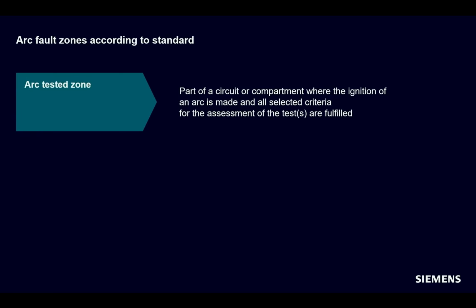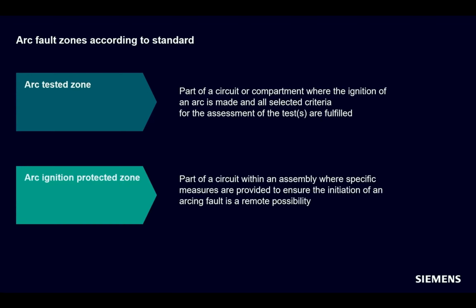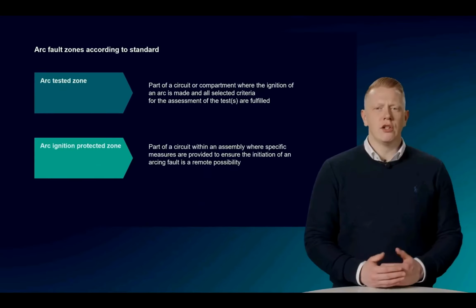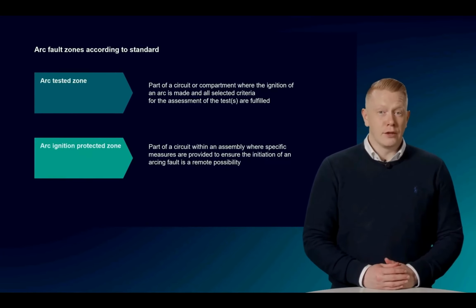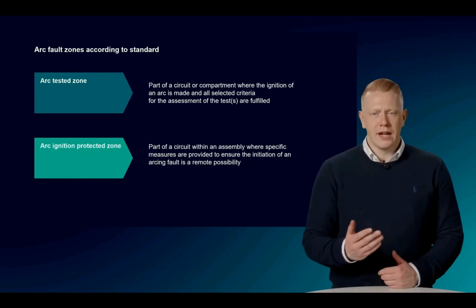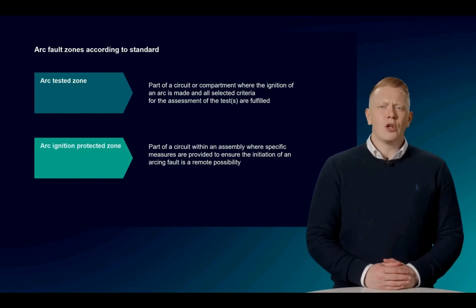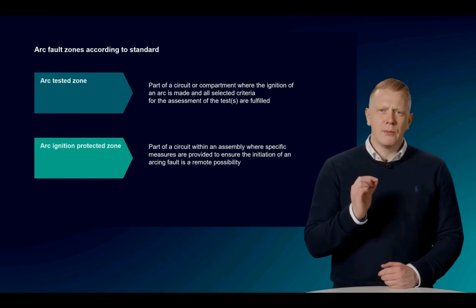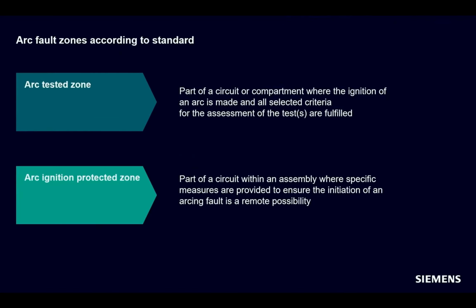And on the other hand, by taking appropriate measures that make the occurrence of an arc fault unlikely. Here, we are talking about an arc protected zone. This can be achieved, for example, by insulating conductors. In a switchboard, you will usually find a combination of both. Arc fault tested and arc fault protected zones. It is also important to define the protection goals in advance.